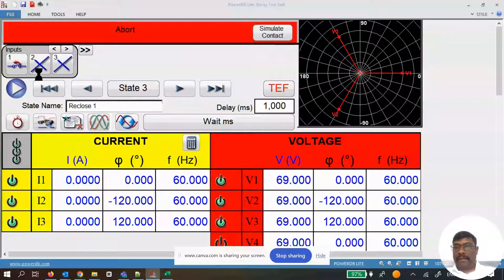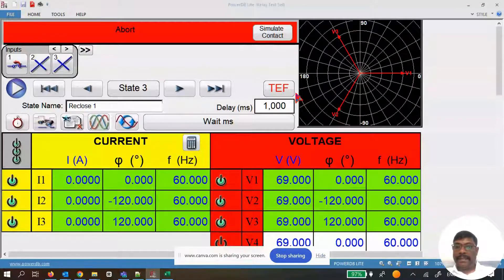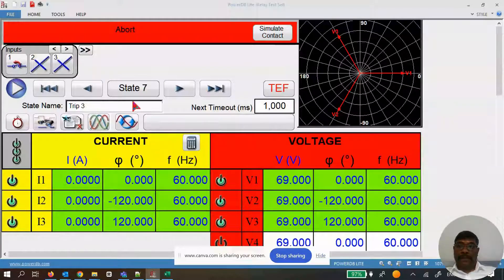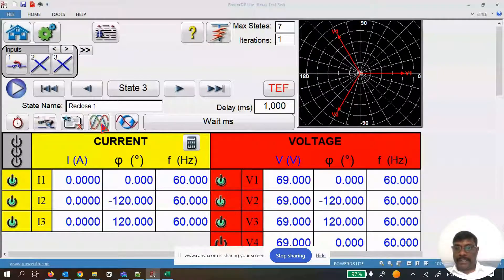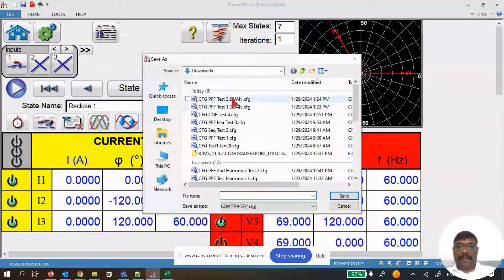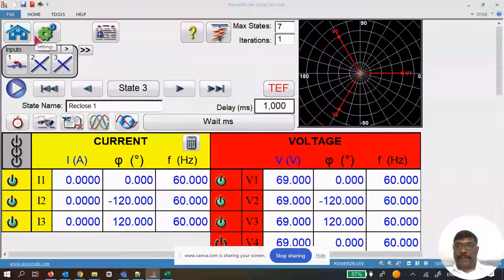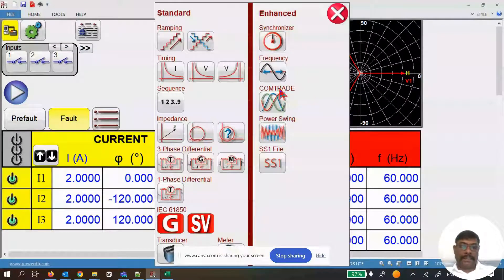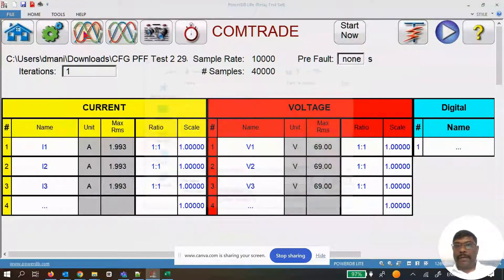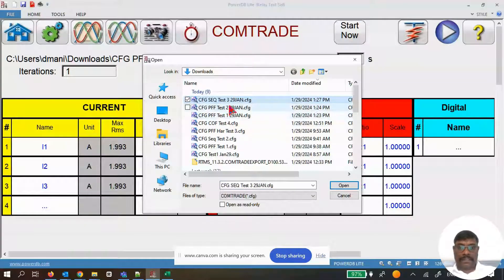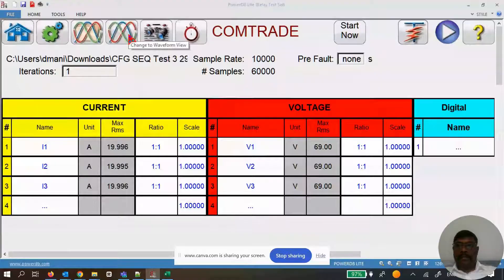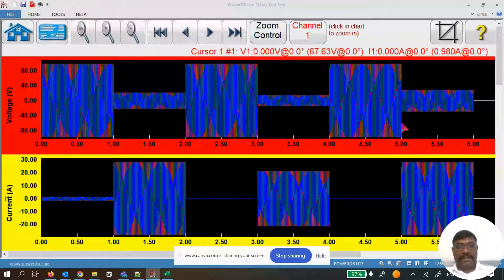When connected to the test set, all state commands are sent in queuing order. In simulation mode the commands aren't fully effective but the test still runs in the background. Once all seven states complete, the comtrade export icon appears. Click it and save the file — for example, 'test three sequencer CFG'. Then go to the home screen, select the test list, pick the Comtrade option, use 'Open Comtrade File', and open the exported sequencer file.